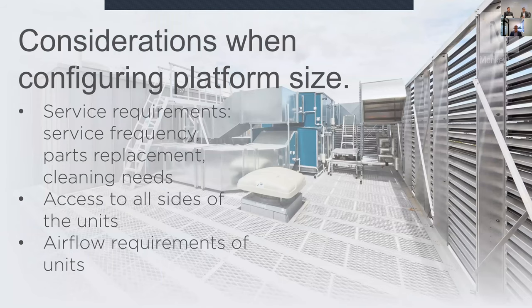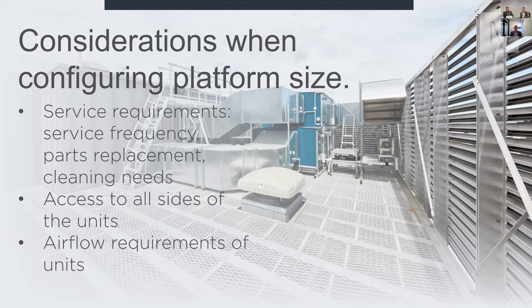When configuring your platform size during the design stage, we need to consider service requirements — the frequency that units or equipment need servicing, what parts may need replacing, and accessible cleaning. Do all sides of units need access or just one or two sides? And airflow requirements — what distance between screens do we need to allow for the airflow?